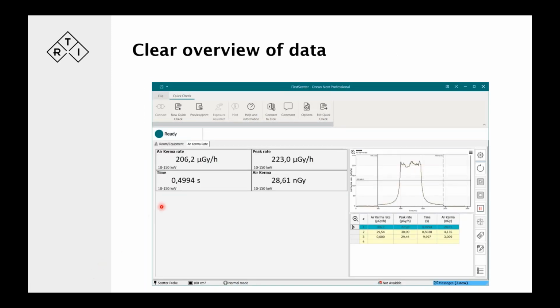rate. You get a clear overview of the data as well here. You've got the dose values, you've got this bit of time. Of course, that's difficult to work with because it may not be correlated exactly to what you have in your panel. But there's an image of the waveform as well, which can come in handy when you're troubleshooting in some instances.